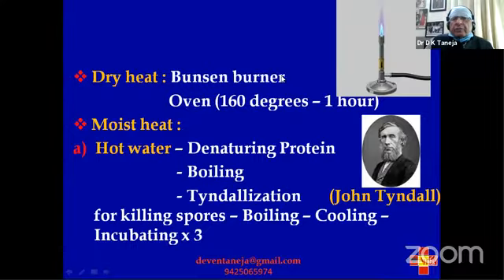So either you can use a Bunsen burner or you use an oven, and for that your temperature must go to 160 degrees and it must be for 1 hour so that you can get a good sterilization. The most important is the moist heat.